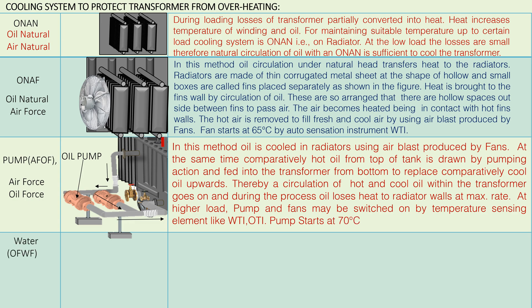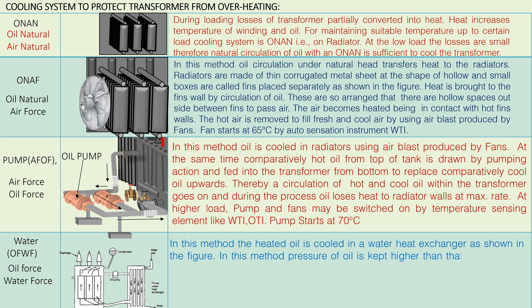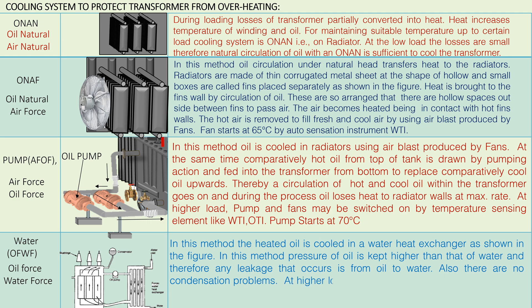OFWF — Oil Force Water Force: In this method, the heated oil is cooled in a water heat exchanger. The pressure of oil is kept higher than that of water, so any leakage that occurs is from oil to water. There are no condensation problems. At higher load, pump and water head valves may be switched on by temperature sensing elements like WTI and OTI.